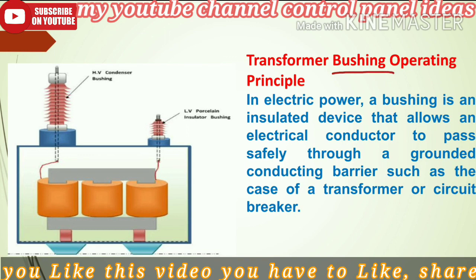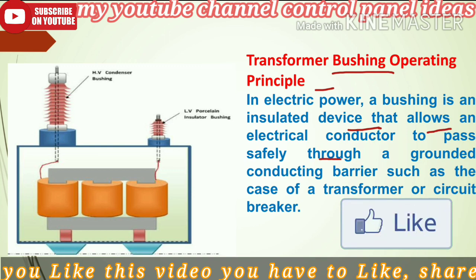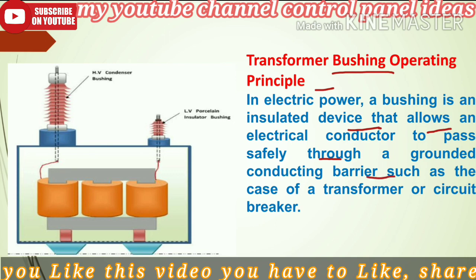Transformer bushing operating principle. In electric power, a bushing is an insulated device that allows an electrical conductor to pass safely through a grounded conducting barrier such as the case of a transformer or circuit breaker.